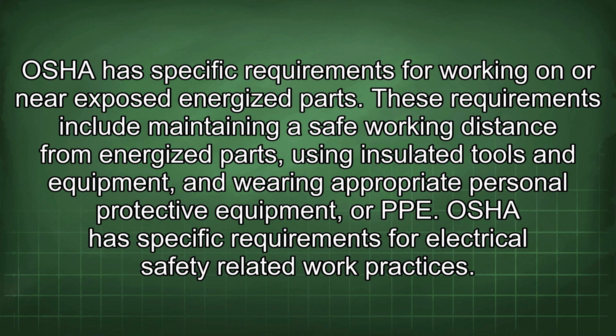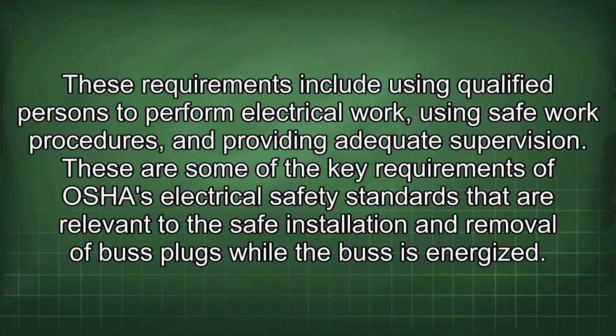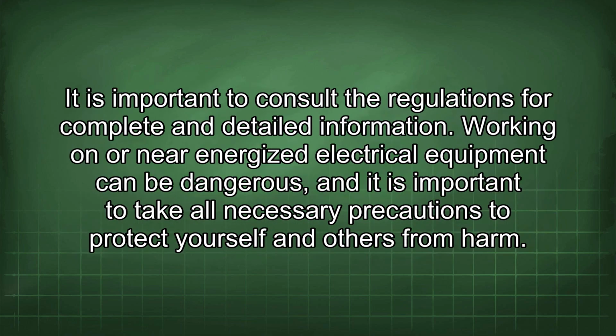OSHA has specific requirements for working on or near exposed energized parts. These requirements include maintaining a safe working distance from energized parts, using insulated tools and equipment, and wearing appropriate personal protective equipment, or PPE. OSHA has specific requirements for electrical safety-related work practices. These requirements include using qualified persons to perform electrical work, using safe work procedures, and providing adequate supervision. These are some of the key requirements of OSHA's electrical safety standards that are relevant to the safe installation and removal of bus plugs while the bus is energized. It is important to consult the regulations for complete and detailed information.